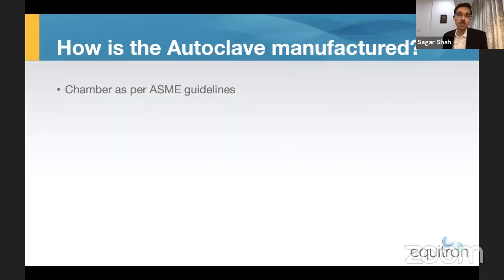Now, in order to ensure a longer lifespan of the autoclave and to be sure that your autoclave chamber is in good shape even after 10 to 12 years, you must ensure that your autoclave chambers are designed as per ASME guidelines, which is the American Society of Mechanical Engineers. At the same time, inquire with your manufacturer whether they have PED certification. A PED certificate, which is not as popular or common as ASME, is important because it's a Pressure Equipment Directive, which is notified by a European body that in effect validates the integrity of the autoclave manufacturing practices. And you can rest assured that a manufacturer with a PED certificate is mandatorily required to conduct certain very stringent tests on the autoclave chamber to check whether they are absolutely safe for labs in case of any unfortunate happening.